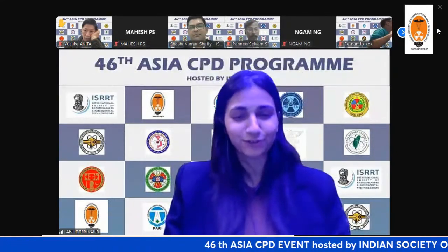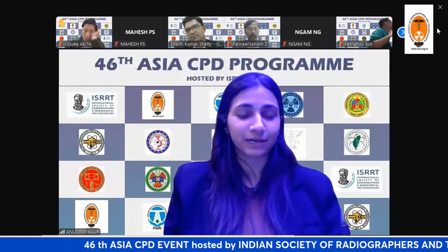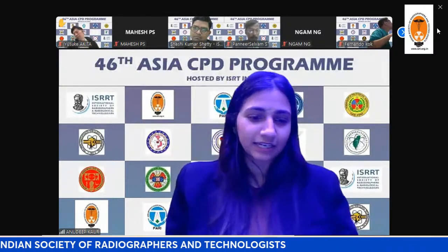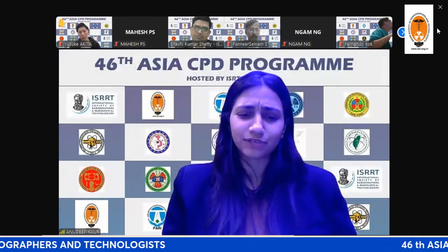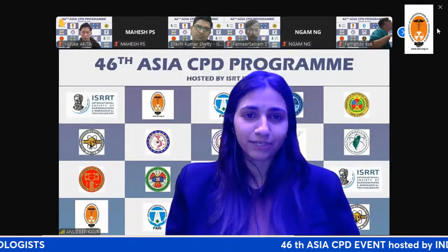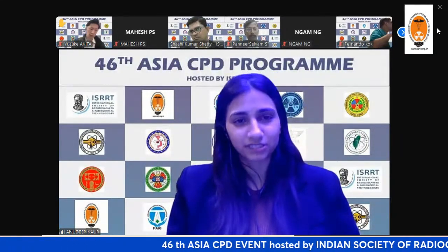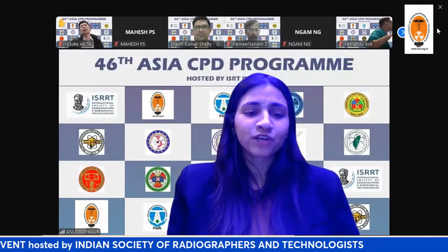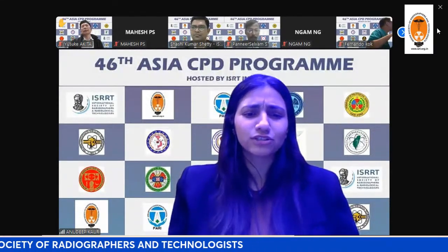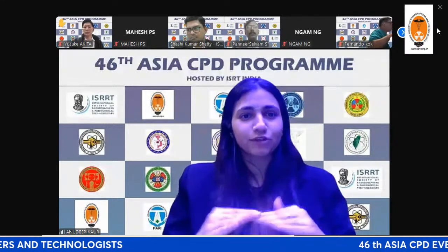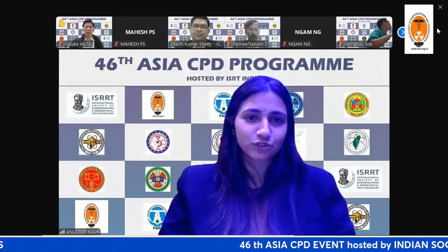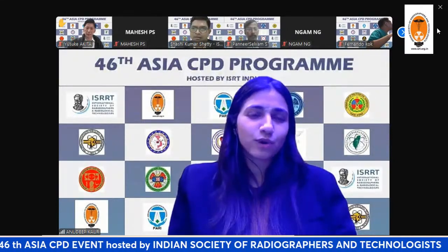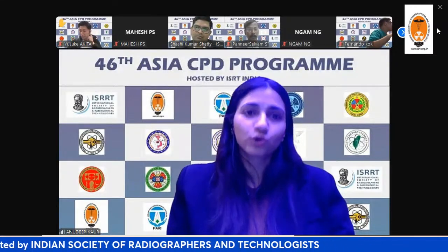Good evening, everyone. Thank you for the opportunity. To answer the doubt, the cushion compression will cause a bit of artifact, and there have been studies conducted around it. If you want, you can read the report on the PubMed study. It found that in 2% of cases, artifact was generated due to the cushion being used. The artifact is basically edge shadowing and blurring. That happens because the cushions are not uniform. Because of the non-uniformity of the cushion when the breast is placed over it, and sometimes overlapping of the material, that might also contribute to the artifact. So these are the 2 artifacts that we have come across while using the cushion compression.